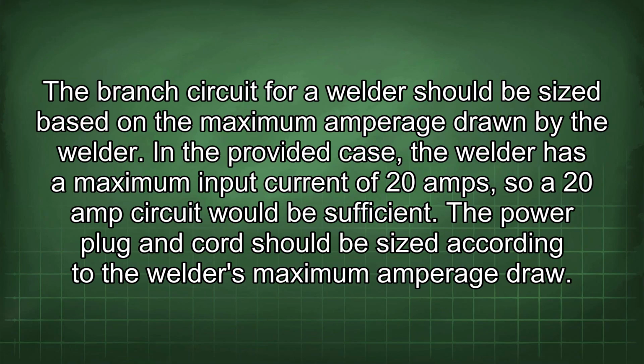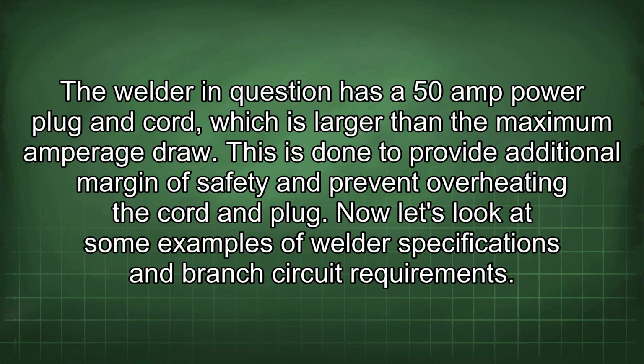Branch circuit for a welder should be sized based on the maximum amperage drawn by the welder. In the provided case, the welder has a maximum input current of 20 amps, so a 20 amp circuit would be sufficient. The power plug and cord should be sized according to the welder's maximum amperage draw. The welder in question has a 50 amp power plug and cord, which is larger than the maximum amperage draw. This is done to provide additional margin of safety and prevent overheating the cord and plug.